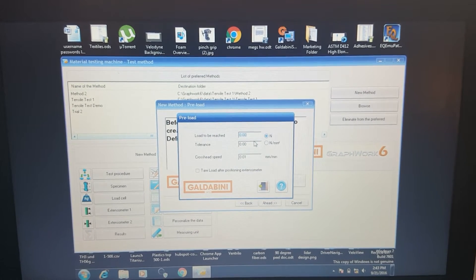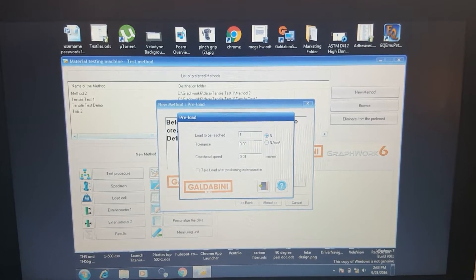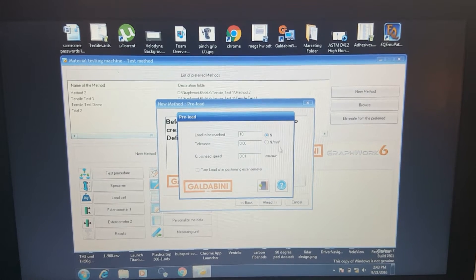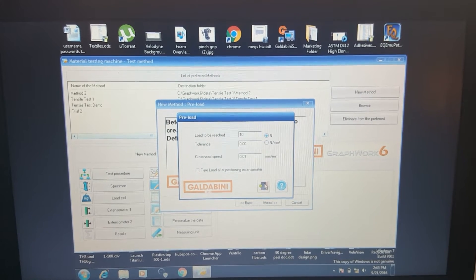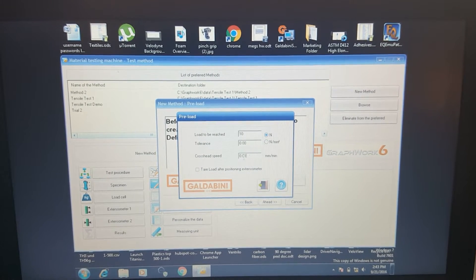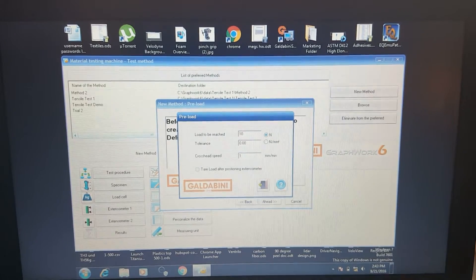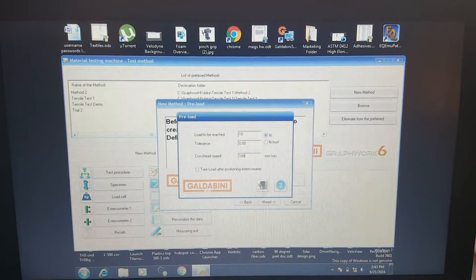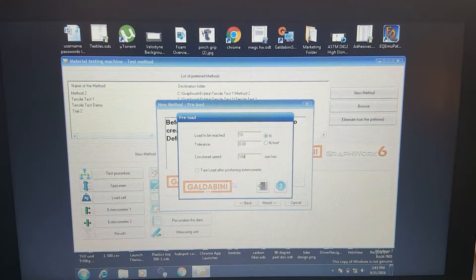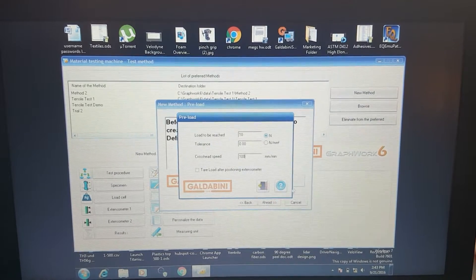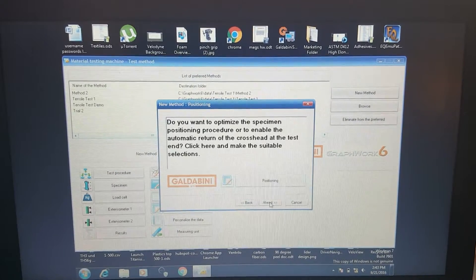This is if we want to set a preload. We'll go ahead and set a 10 newton or about two pound preload, and that load will apply at 100 millimeters a minute.